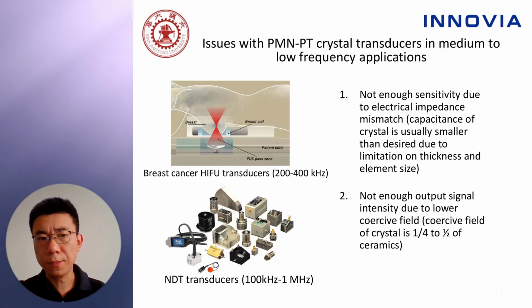These applications include breast cancer HIFU transducers, which are from 200 to 400 kilohertz in frequency, and high-performance NDT transducers, which are from 100 kilohertz to 1 megahertz in frequency. First issue, not enough sensitivity due to electrical impedance mismatch. The capacitance of PMN-PT crystal is usually smaller than desired due to limitations on thickness and element size, limited by bandwidths.